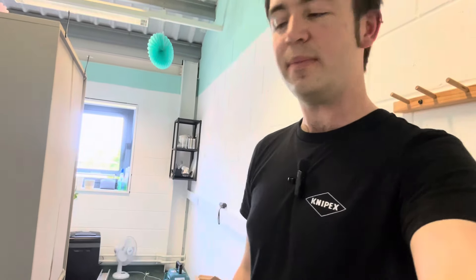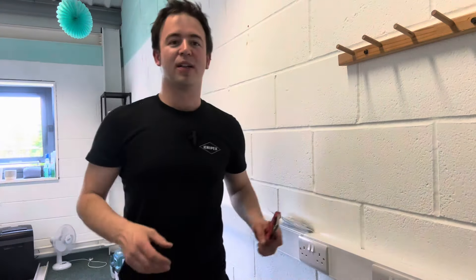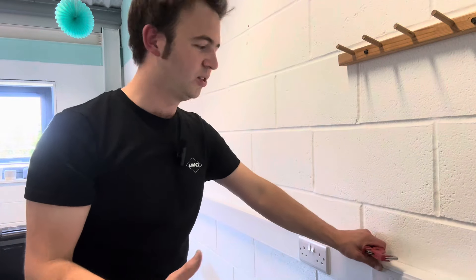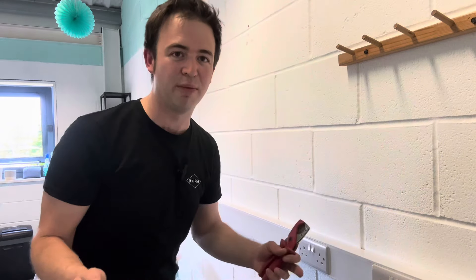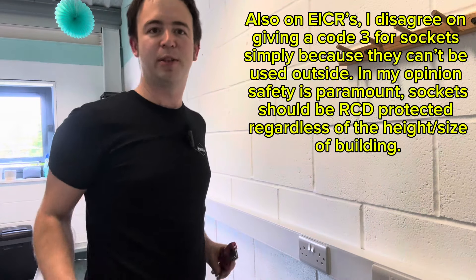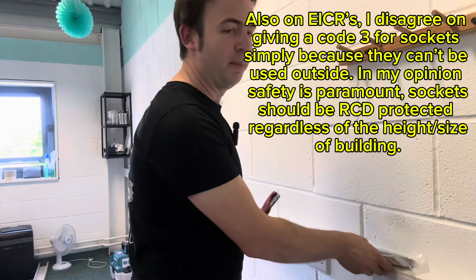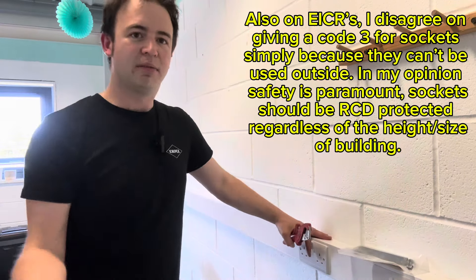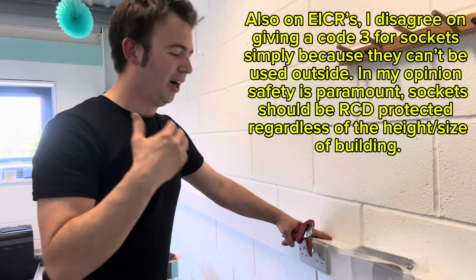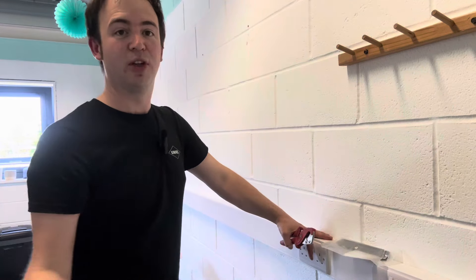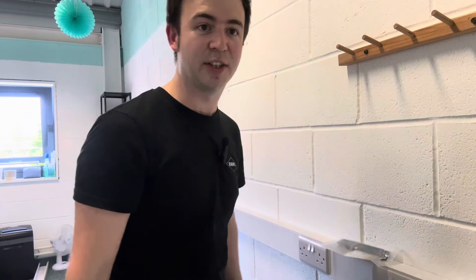I've got to fit this RCBO pod. I'll talk more about that. This is on a first floor, and I am aware that some sparks, when they work on circuits or alter circuits or make additions to circuits, because it's not on the ground floor, they think it doesn't need RCD protection. In my opinion it does, but there's some people who go, well it's first floor, second floor, no, doesn't need RCD protection. I disagree. It requires additional protection.